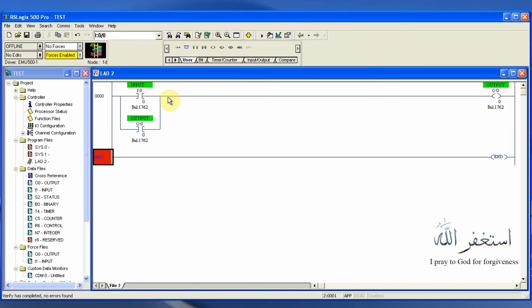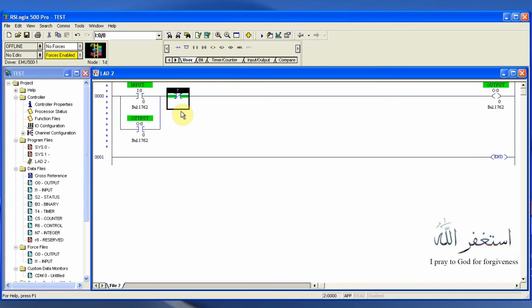Once it gets latched or permanently turned on, we cannot turn it off. To turn it off, we have to put a normally closed contact here. Whenever we have input at this contact, it will open and cut the path, unlatching our output O0/0. We will use I0/1 as the reset input.